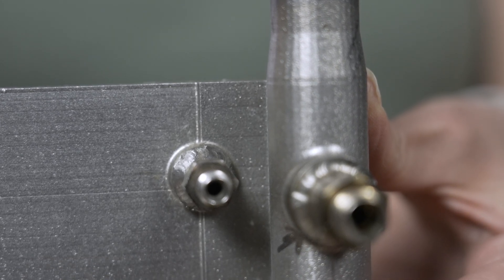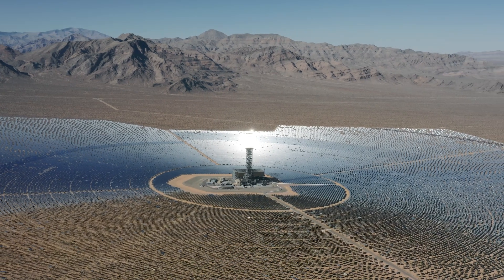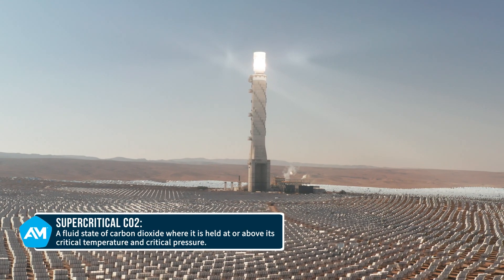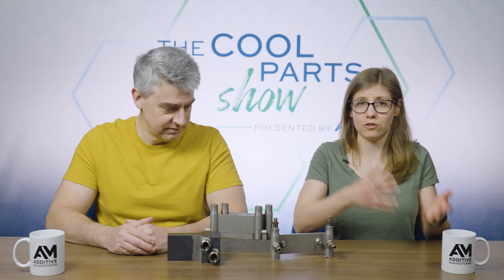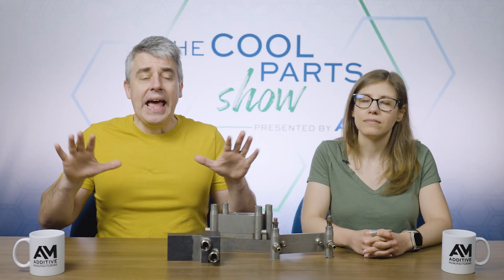In this case, it was a materials issue, and to understand why, we have to talk a little more about the application. All of the heat exchangers and heat sinks here were created as demonstrators for the solar industry, specifically for concentrated solar power, dealing with lots and lots of energy. Heat exchangers in this space commonly use supercritical CO2 as an exchange mechanism to capture energy and transfer it to a storage medium, usually something like molten salt. In short, these heat exchangers are operating at extremely high pressures, very high temperatures — around 800 degrees centigrade or more, and pressures around 200 atmospheres. That combination of heat and pressure means that creep is a potential failure mode, and a very creep-resistant metal is what's needed.